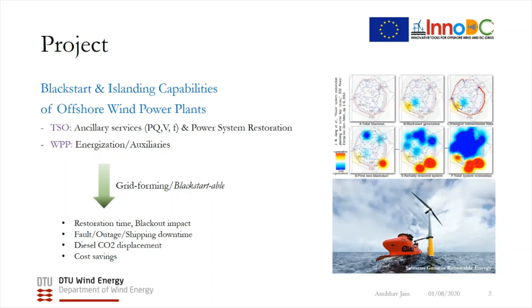For the wind power plant operator, a self-energizing wind turbine or grid-forming wind turbine can help minimize the dependence on the diesel generator offshore, because it can energize the offshore collector cables, the transformers, and even operate without requiring an external network. This can reduce the downtime due to shipping during refueling, save costs because of the freeing up of offshore space if a diesel generator is not required anymore, increase reliability, and it's also important that the carbon emissions associated with the operation of the diesel generator are displaced.